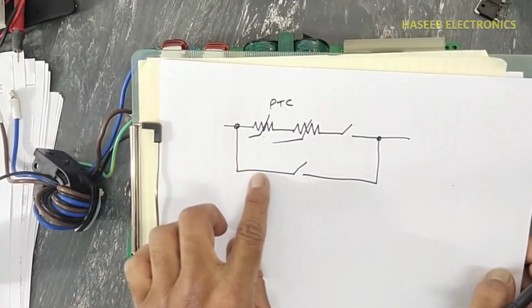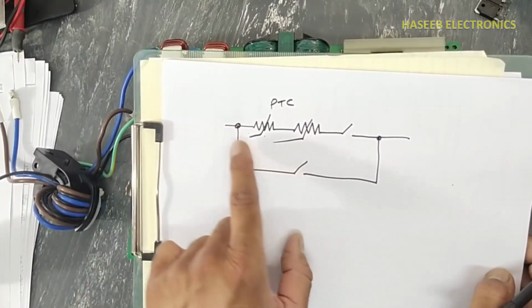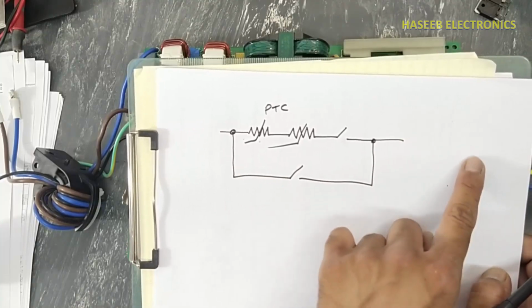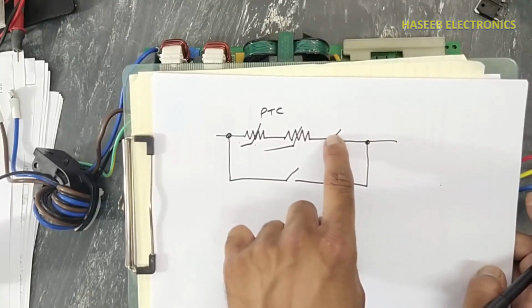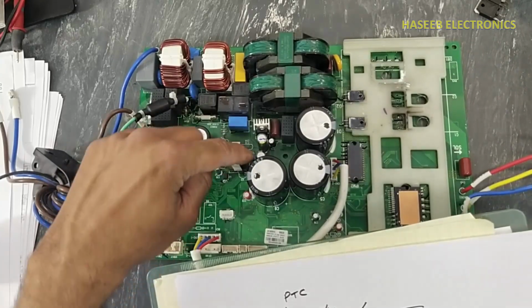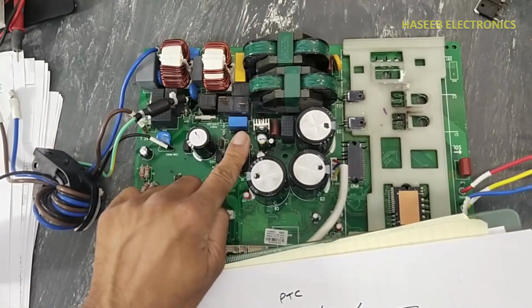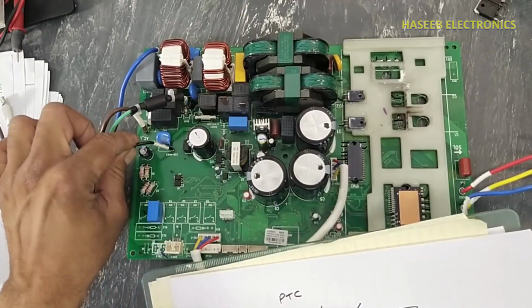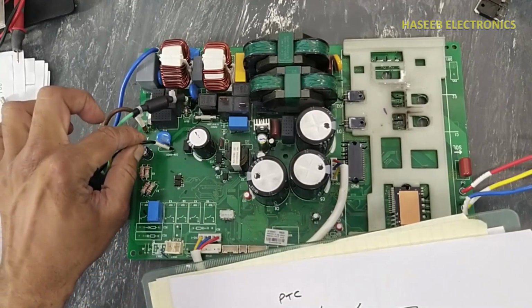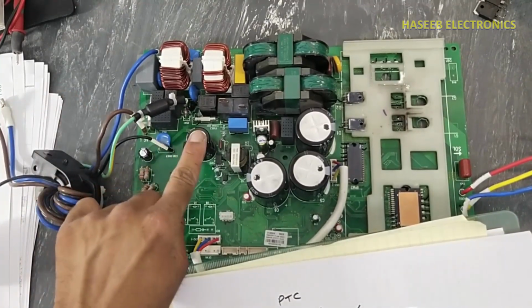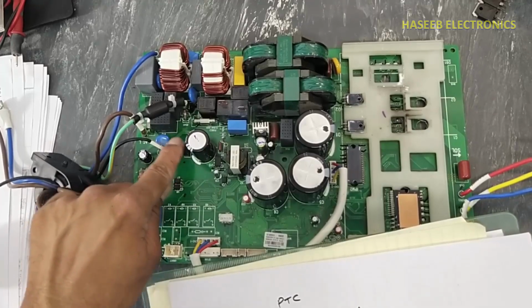At that time, full current will pass to the next circuit. To turn on this relay, we need to turn on this power supply. To turn on this power supply, the indoor unit must be connected. Voltage will reach here. It will charge this capacitor by means of this PTC.